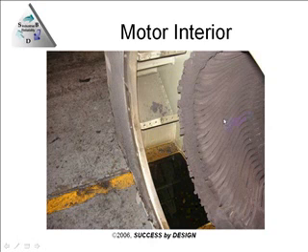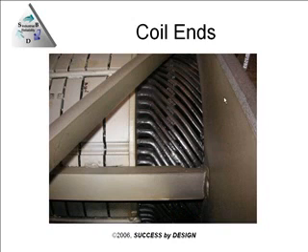I would have expected, as a rewinder, to see a lot more blocking than this, and more than one surge ring. I only had a little bit of blocking and one surge ring. Now, in this picture, you can see what the blocking looks like.